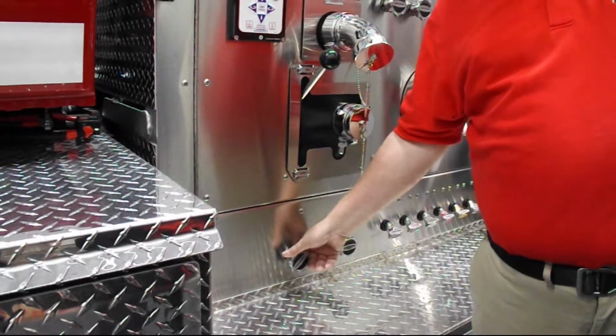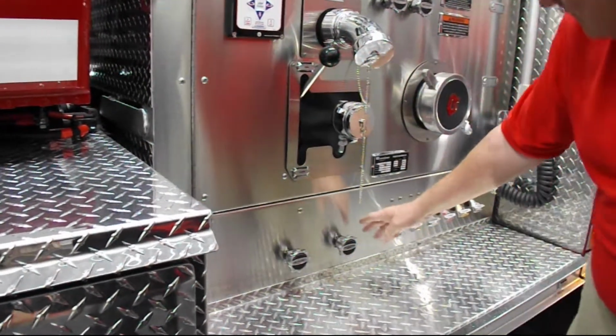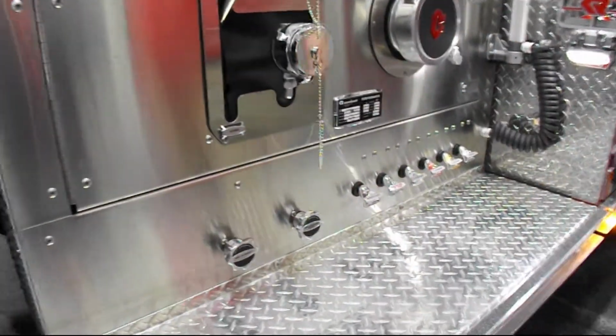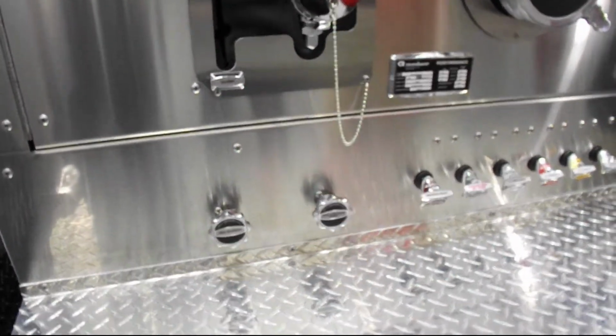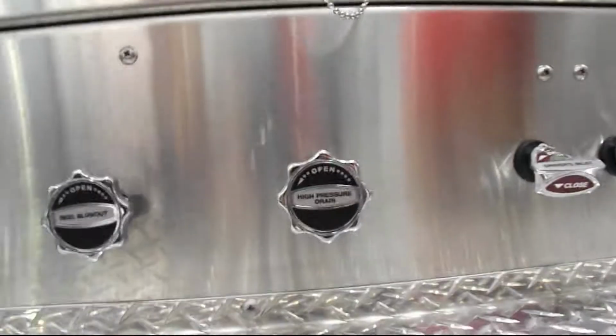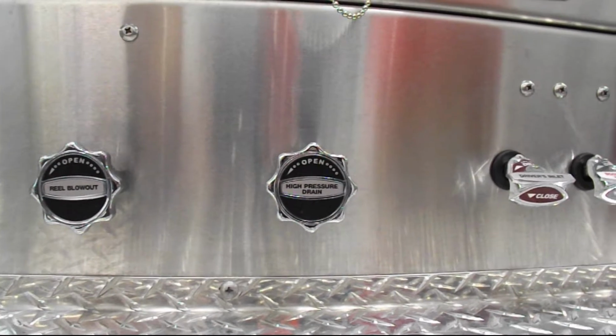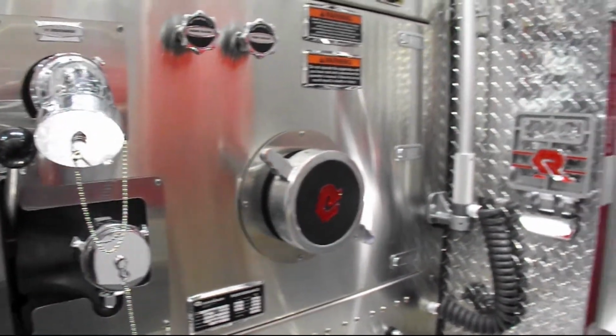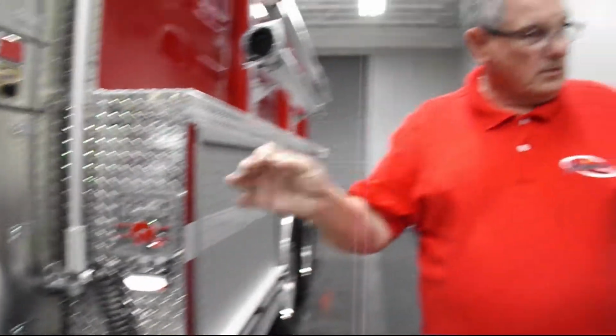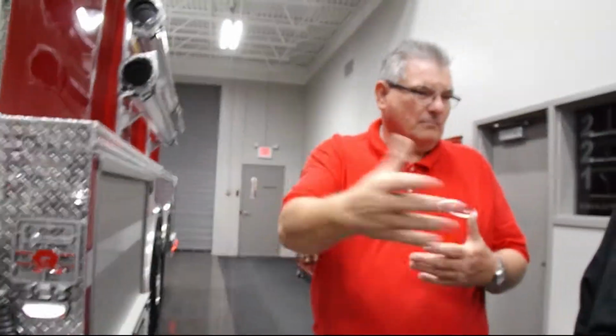Yeah, because she's straight chassis here. This is the high pressure drain. You got to make sure during the winter you get all that stuff open, because there's always water on the high pressure side. A centrifugal fire pump is water cooled, so we don't send much through there. If you use a boost line, there'd be some water coming out, but once you get high pressure, it's a whole different story.